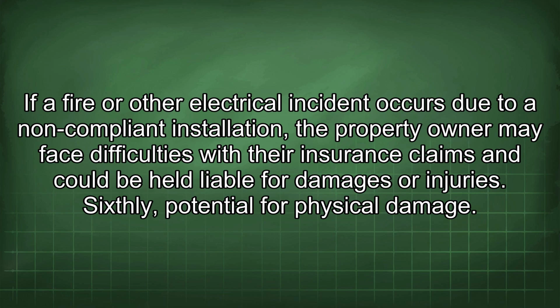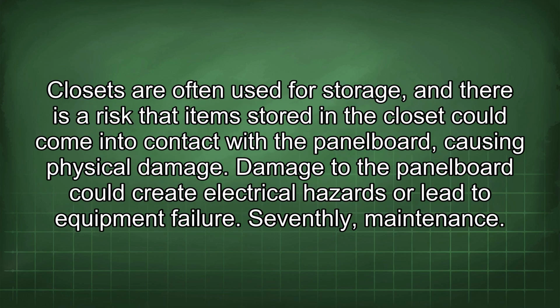Sixthly, potential for physical damage. Closets are often used for storage, and there is a risk that items stored in a closet could come into contact with the panel board, causing physical damage. Damage to the panel board could create electrical hazards or lead to equipment failure.